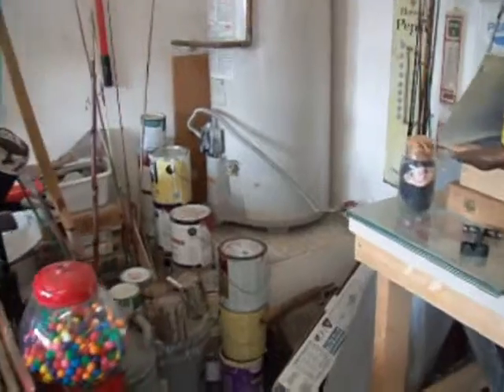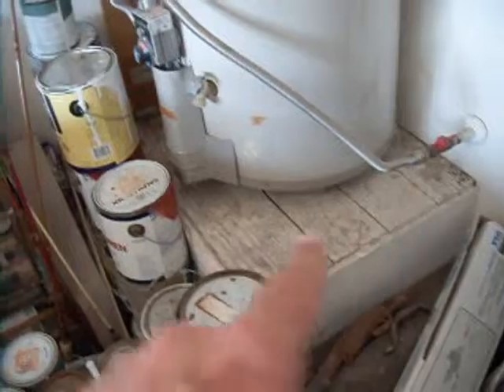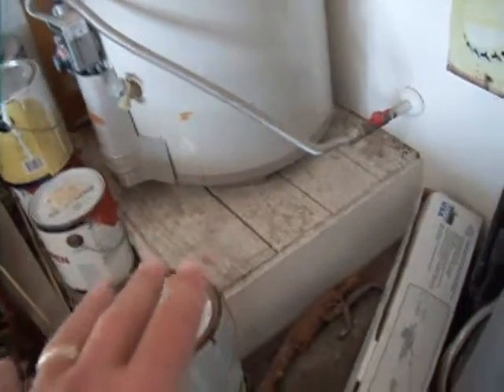This is the water heater inspection. What I'm looking for is correct installation — it's not installed correctly. It hasn't got a safety pan, and it should have one.